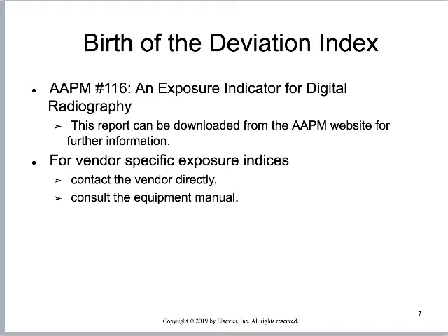The problem, as I see it as an x-ray tech, is that the AAPM and the ASRT have very little conversation going on. Every now and then I get angry nerds who write me hostile letters about how the deviation index wasn't adopted by action — okay, thank you, there's not really a conversation going on. But the AAPM released report number 116 detailing their way of creating an exposure indicator, and that's what we're going to talk about right now — what that is and how to use it.